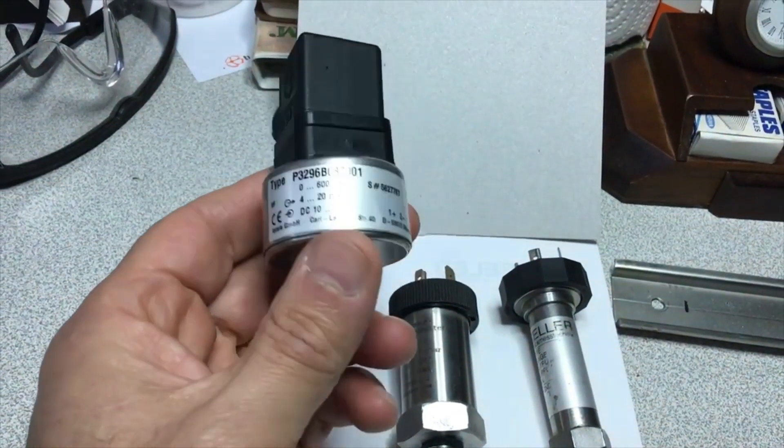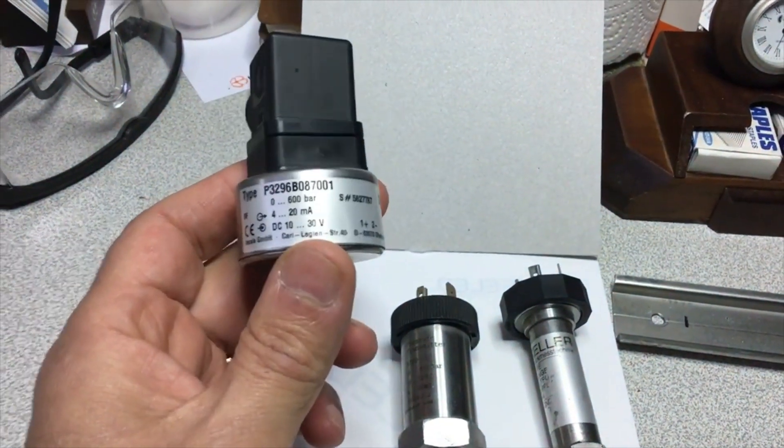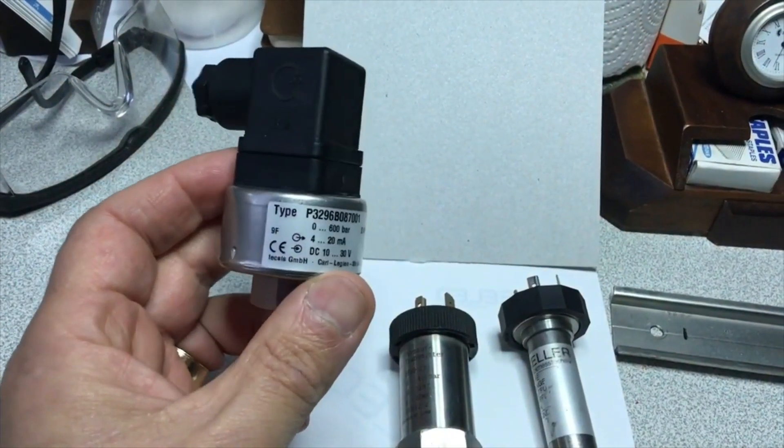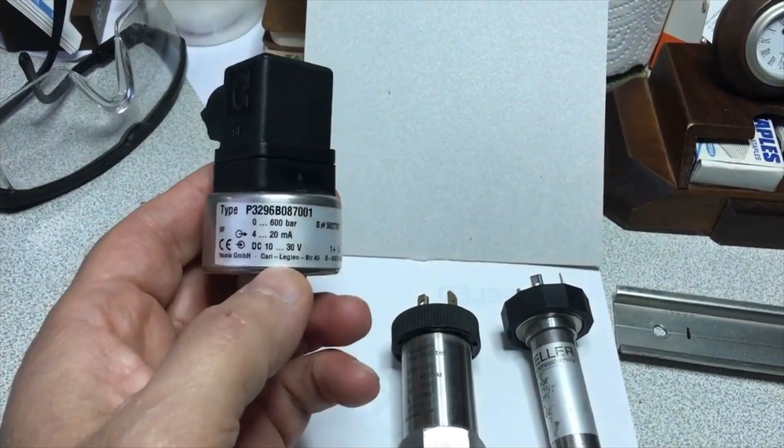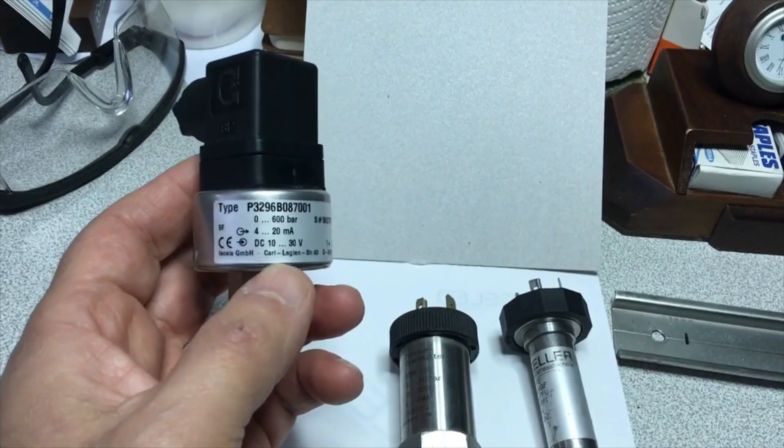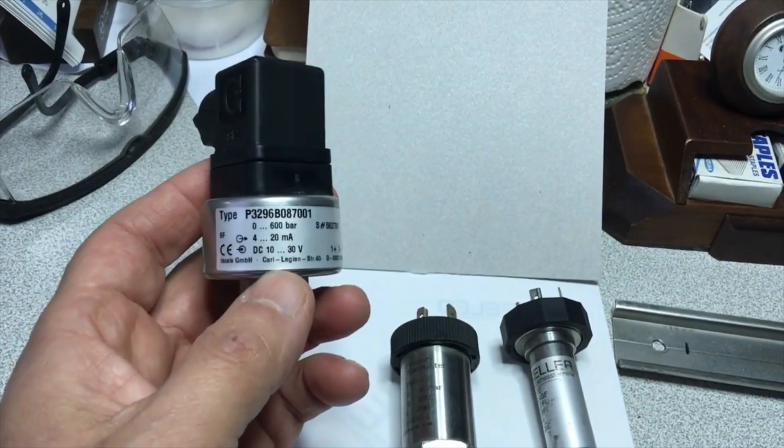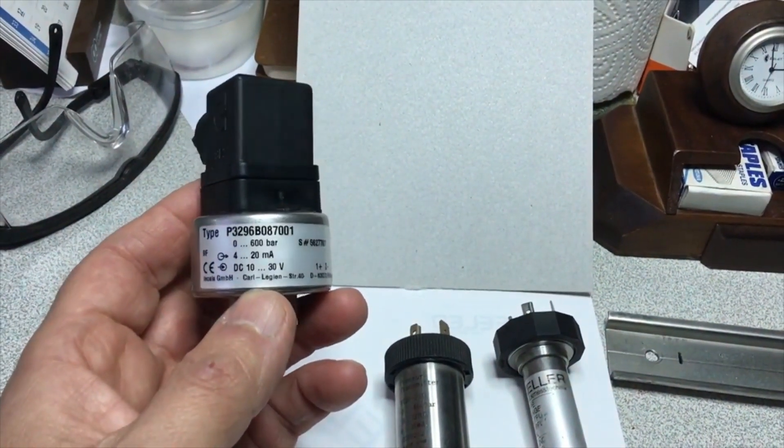Let's examine a newly purchased sensor that has not been used in my hand. It appears to be high pressure in the sense that it can measure pressures between 0 to 600 bars, that is, suitable for hydraulic systems. If it was pneumatic, the upper limit would be lower.